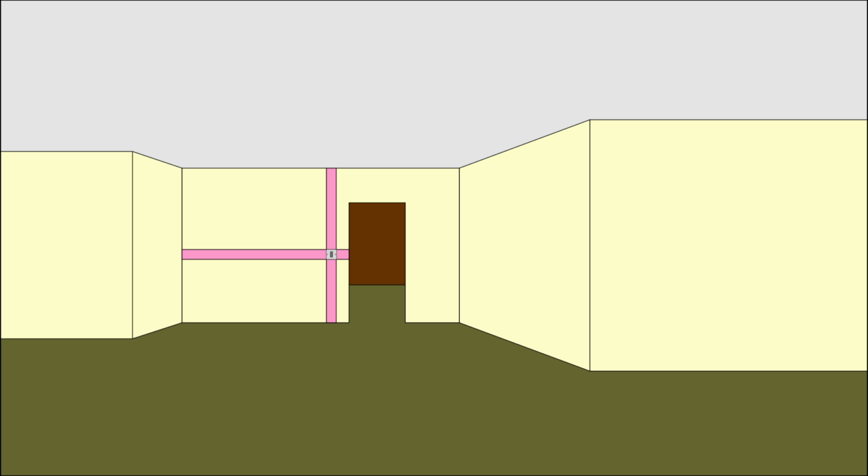Now the fun part of these zones from accessories is the fact that if you've got, say, a light switch, as we've got here, and it's on a wall, and the wall is less than 100mm thick, and there's some kind of opening, such as a doorway or window or something, so you can actually see around the other side very easily, then the zones shown here in pink do extend onto the other side of the wall as well.